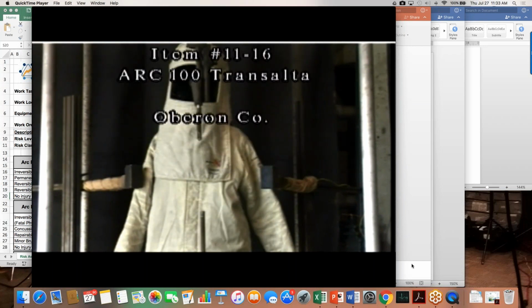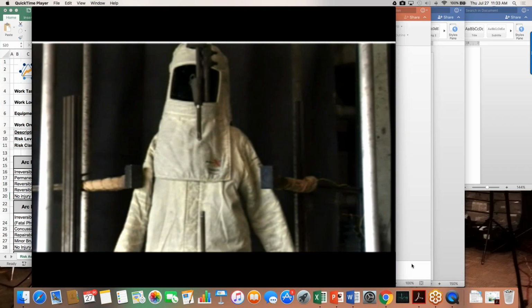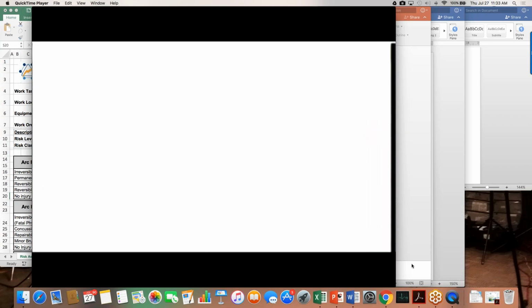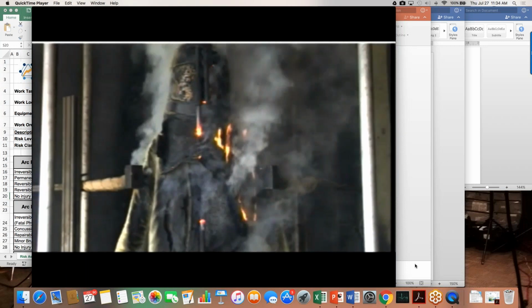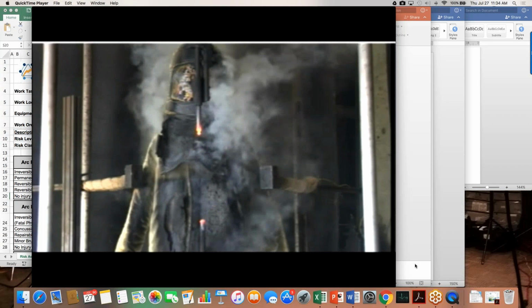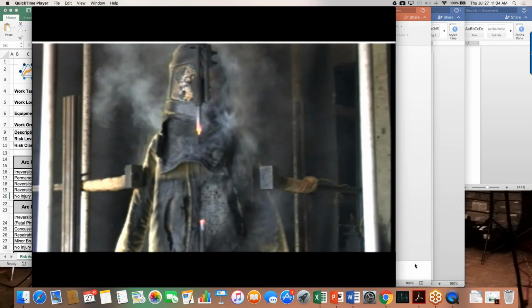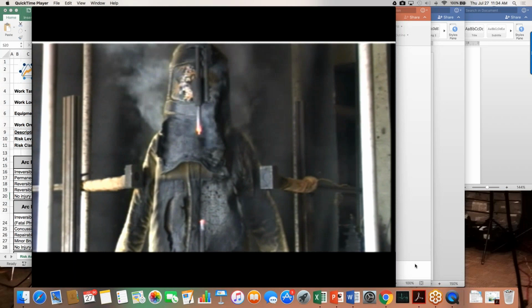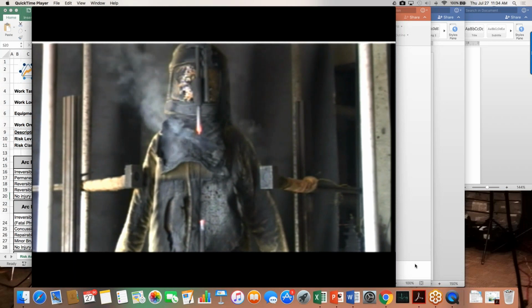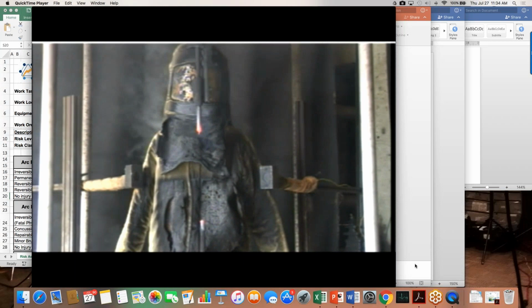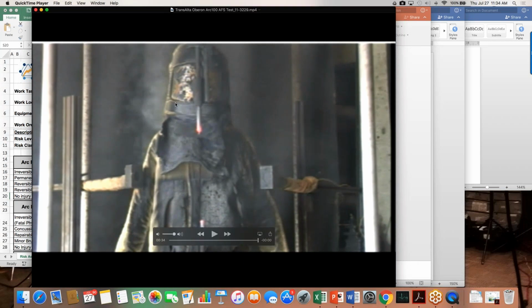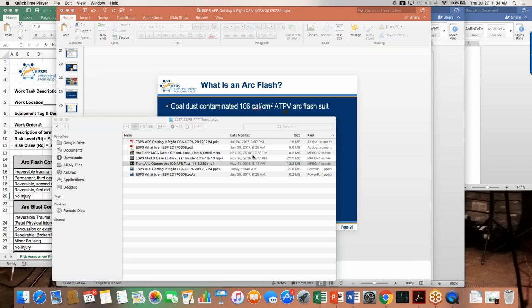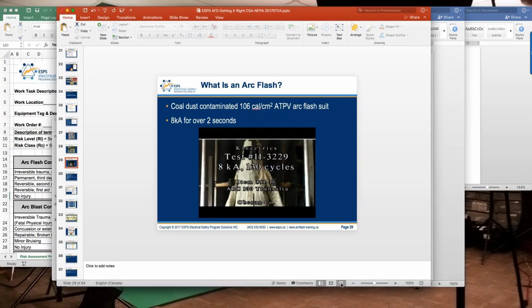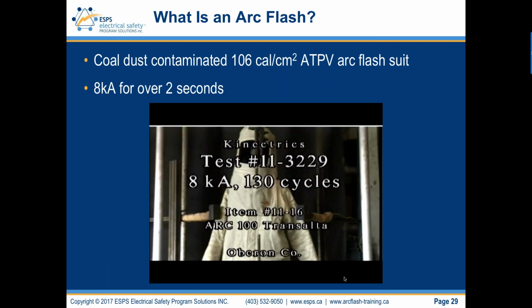So the issue here is the contamination. We shouldn't have PPE in use that's contaminated. What we do understand is, does it still perform? So this arc flash suit performed. What you see on the screen is what will happen to an arc flash suit when it's exposed to an arc flash. This was over its actual arc thermal performance value, 106 calories, and with the fault current and fault clearing time that they had to maintain at the Kinectrics lab to achieve greater than 106 calories, I was told that it probably was between 120 and 140 calories. So that was a pass.